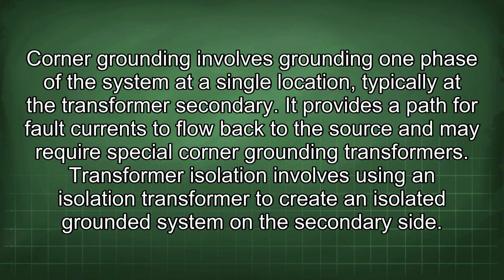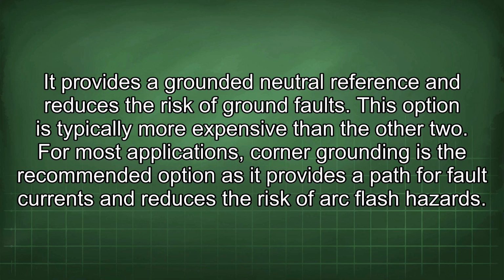Transformer isolation involves using an isolation transformer to create an isolated grounded system on the secondary side. It provides a grounded neutral reference and reduces the risk of ground faults. This option is typically more expensive than the other two. For most applications, corner grounding is the recommended option as it provides a path for fault currents and reduces the risk of arc flash hazards.